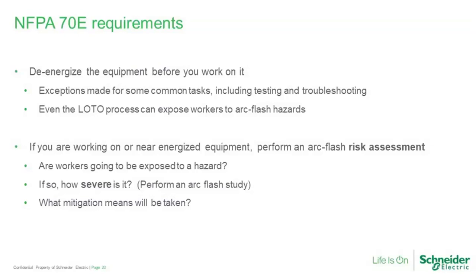But if you're doing some kind of task, whether it's testing or whatever, that may expose you to a hazard, the next step would be to figure out how severe that hazard might actually be. So maybe that's where you get involved in performing an arc flash study. And then finally, the third item: what mitigation means would you take in order to reduce the risk to the worker? I mentioned, and I don't have it shown here on the slide, OSHA requirements for utility transmission and distribution systems. Just to mention those for completeness.